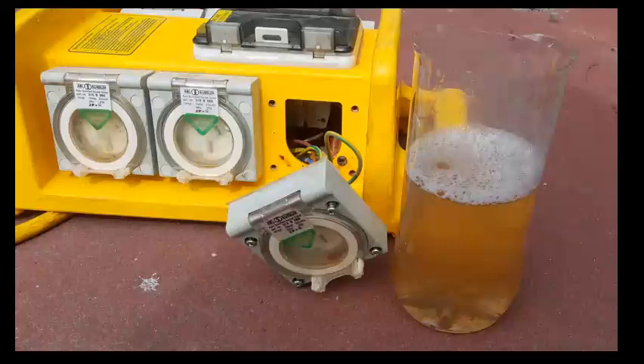These are designed to trip, like a circuit breaker but a bit more involved, if anything was to happen, if a lead was cut or there was some issue within the appliance you're using. Our test equipment can test these RCDs and put them through a fail system to make sure they do trip, with a trip time within 30 milliseconds, a very short period of time, to make sure that if anything was to happen, it's not likely to cause an electric shock to the person using the appliance.